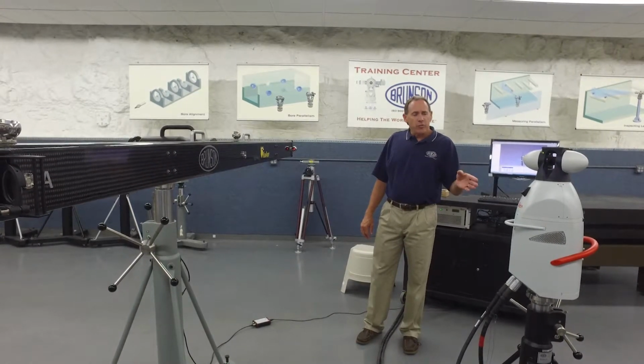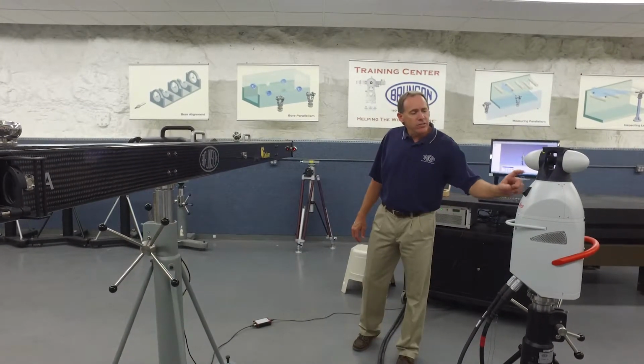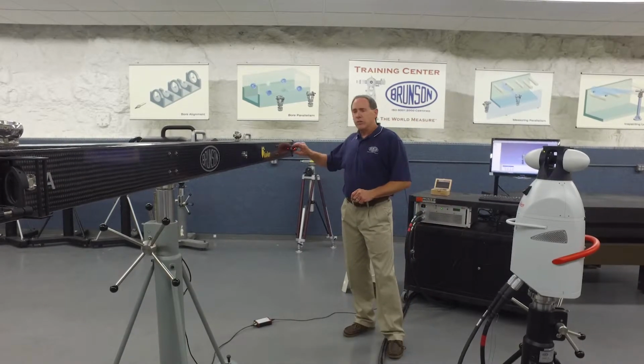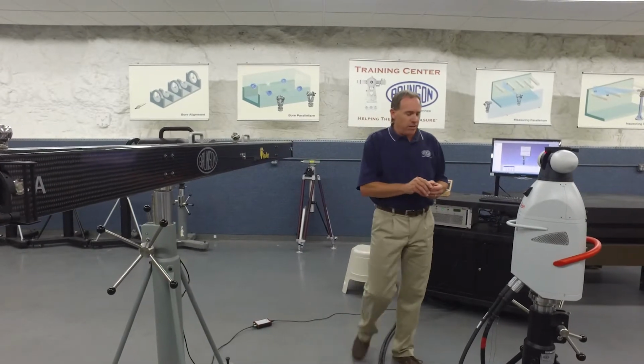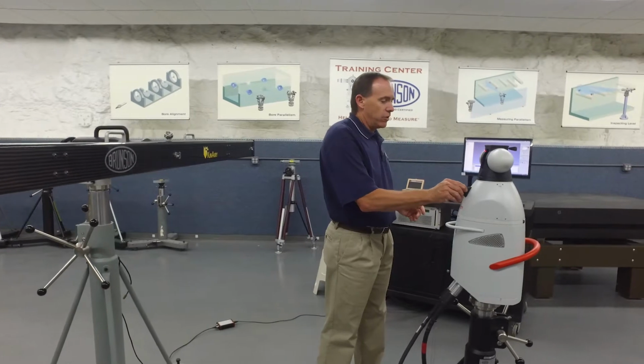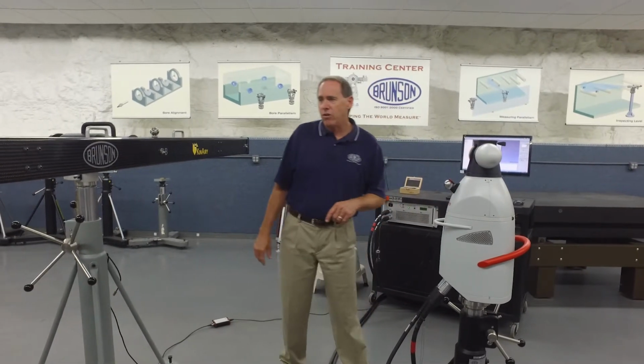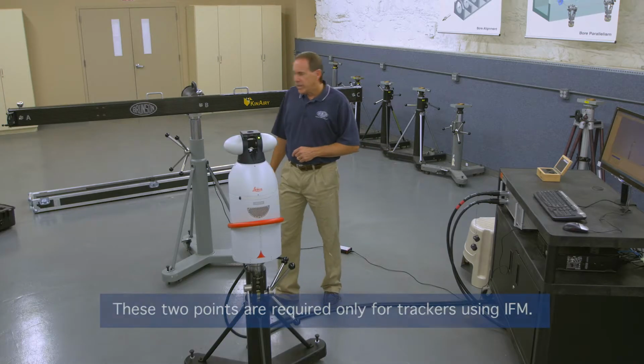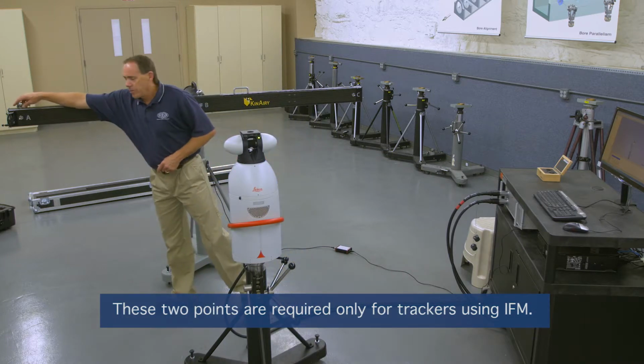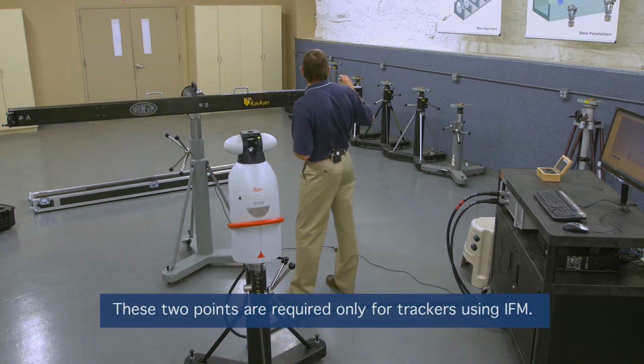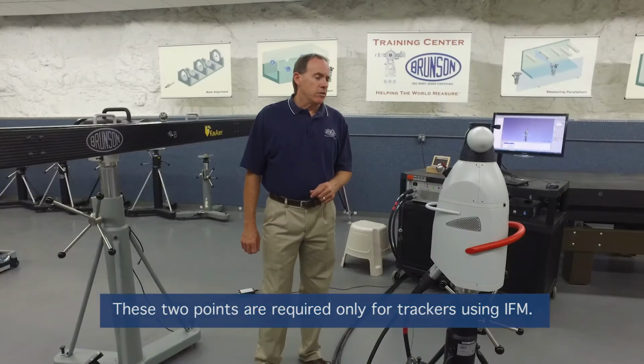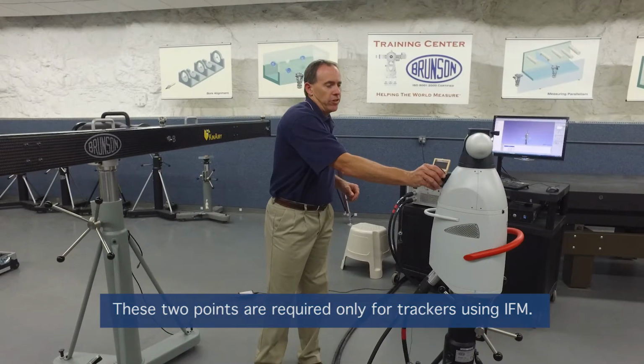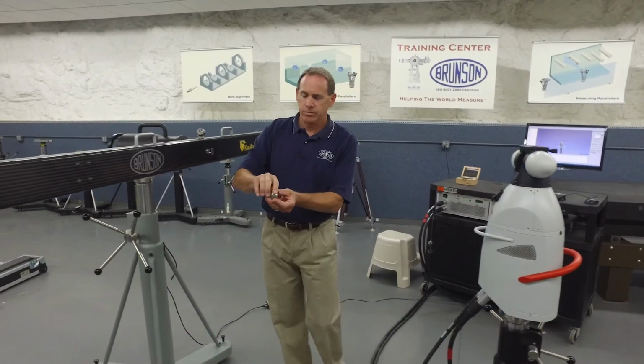Because this is an IFM tracker, there is a bird bath distance that's important to account for. So to do that, we're simply going to break the beam. Because it's in IFM mode, it's going to go right back to the home position and it's going to rehome there. And our test for this is going to be to take a measurement at point A and point C. So let's take those last 2 measurements as a part of our calibration process.